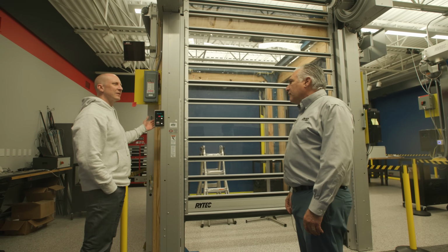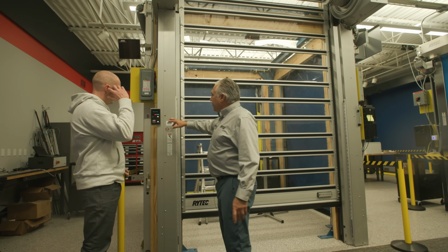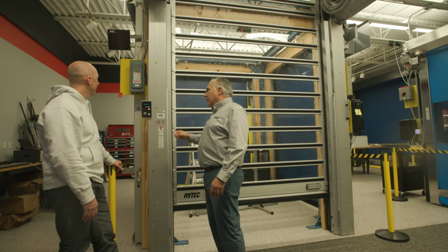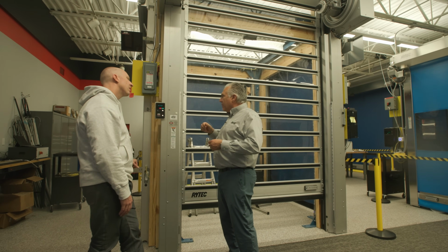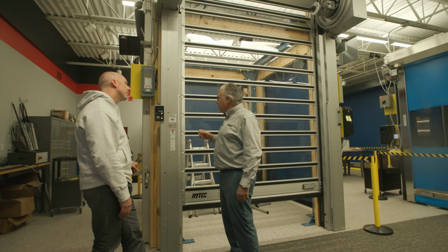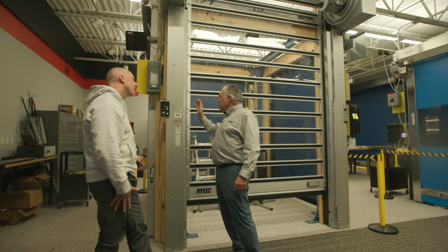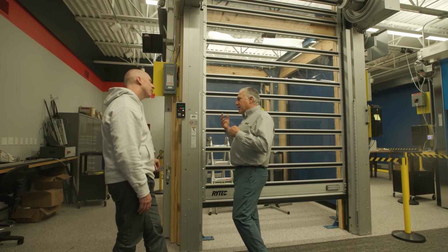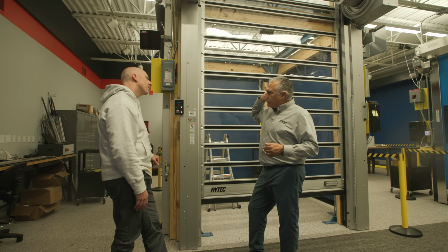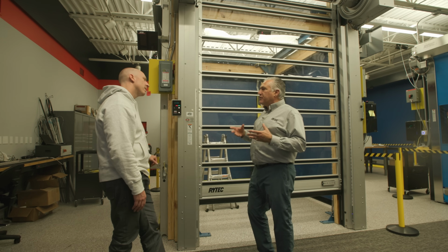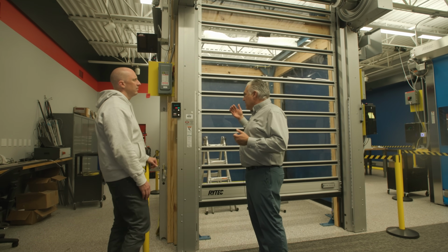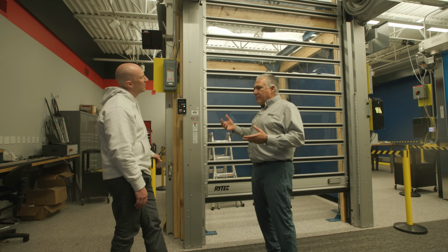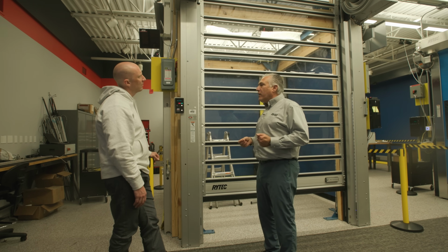Then is it like a Cat 6 wire that runs from that to the brain? Correct. So this is actually on a CAN bus system. So it's a Molex type. Correct. We have small M8 or M12 connectors, depending on the number of devices involved. When we introduced smarts around that, because of the amount of information being transferred between the sensors and the controller, we went with a CAN bus system so that we could process that information more quickly. And the CAN bus makes the consistency of all of the multiple devices work well together.